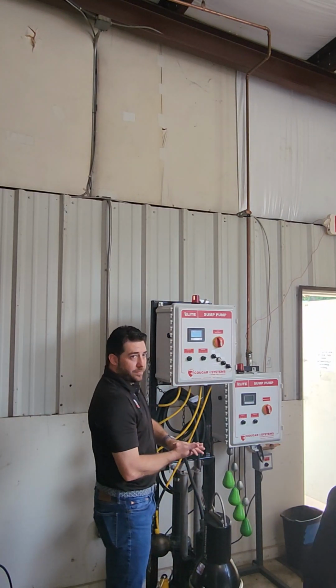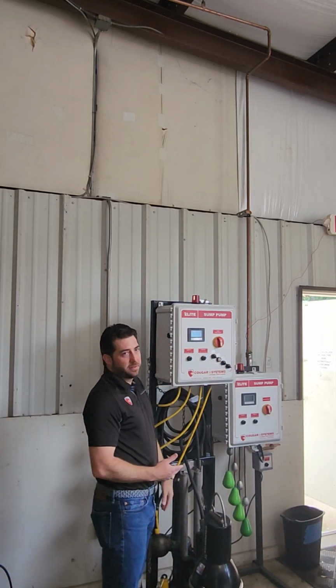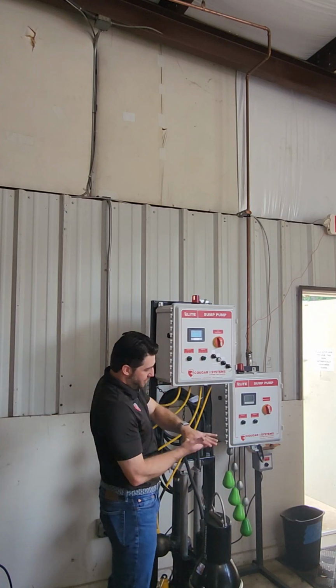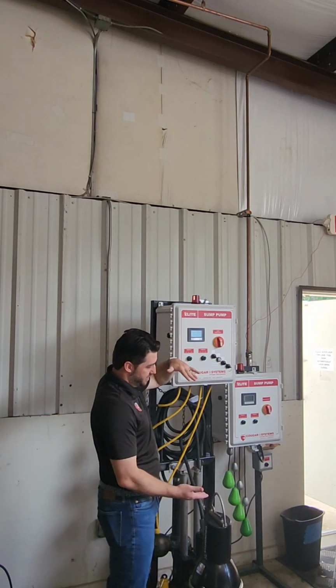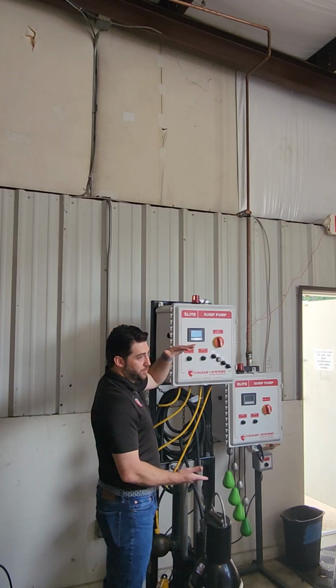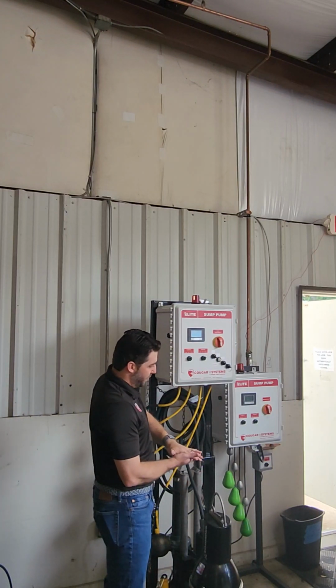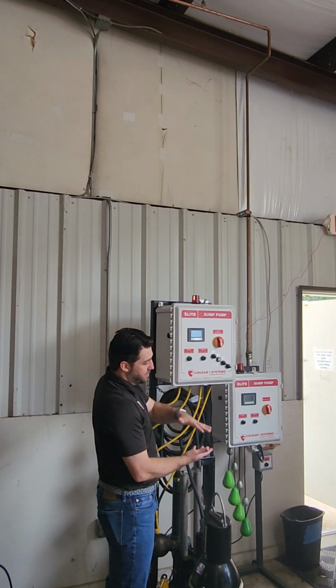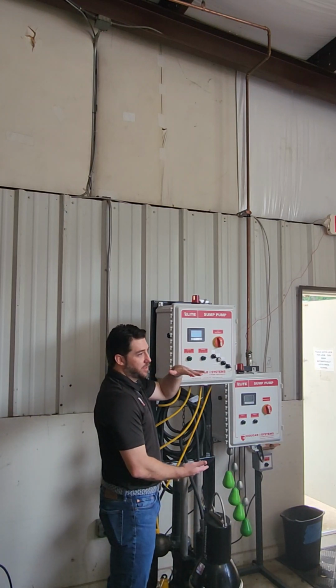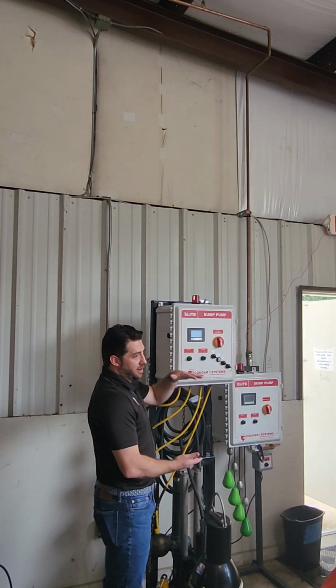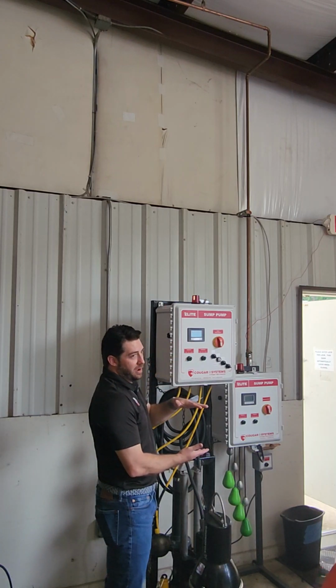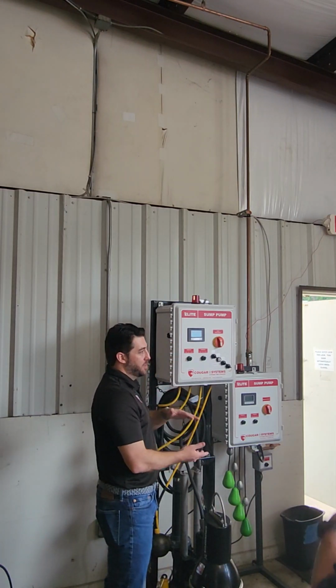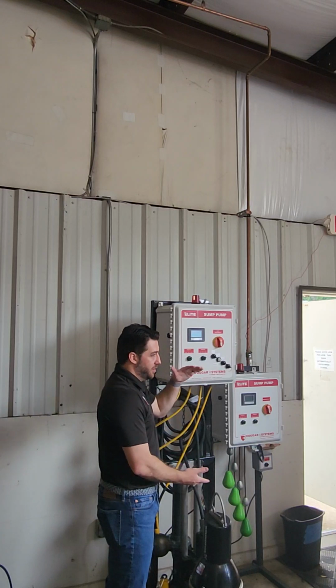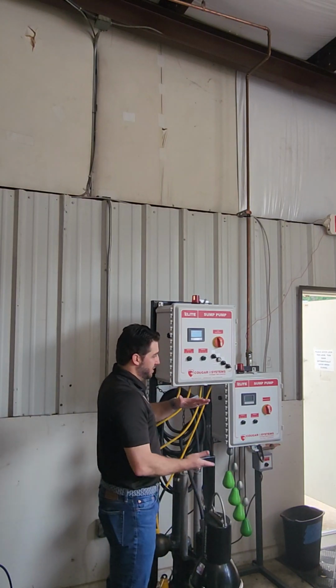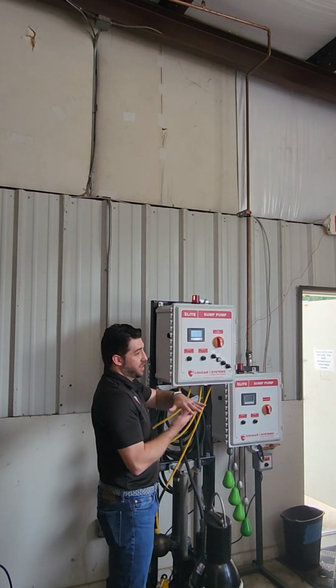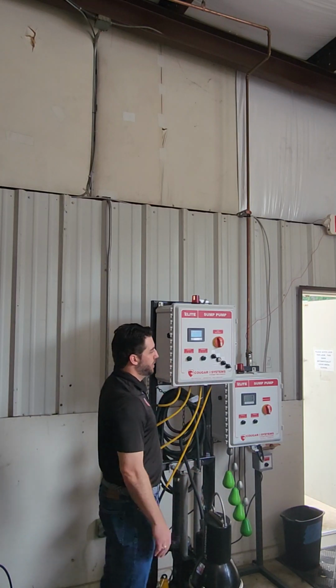When you say invert, you mean the inlet of the water? Inlet, yeah, the inlet of the water coming in. That invert elevation coming down from wherever that inlet is in the pit. So that's your usable space. Ideally you want that first pump down range to be as long as possible, especially if you have a grinder. Especially if it's an active pit, you don't want these things to start on, off, on, off, on, off, short. So EJ, I don't know if you have any recommendation on that, but just try to get as much pump down on that first pump.